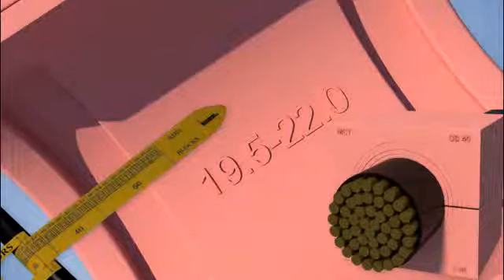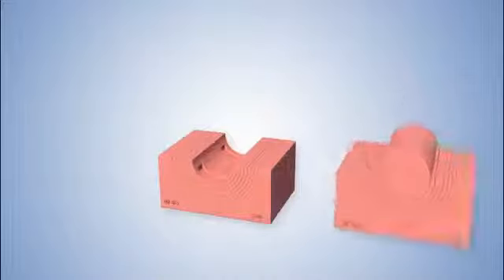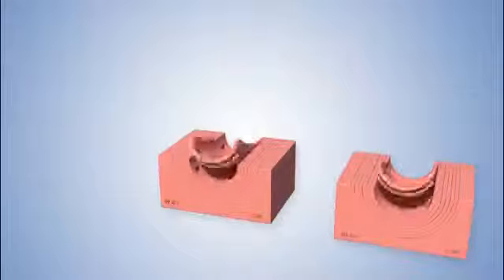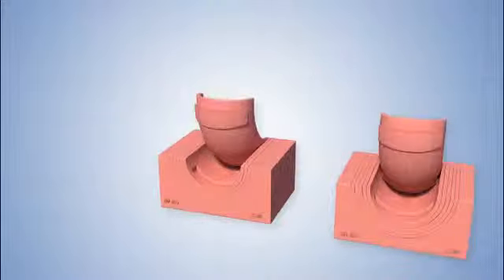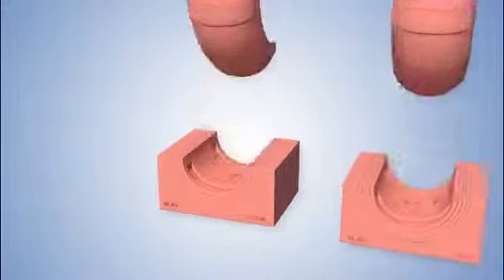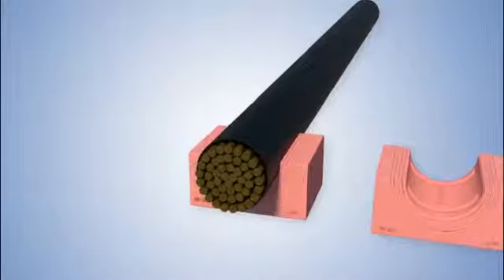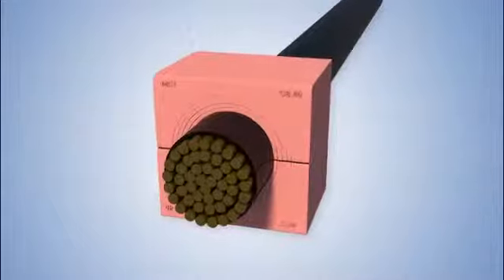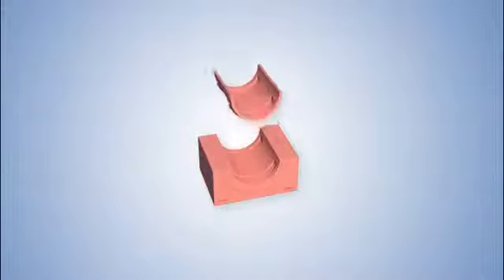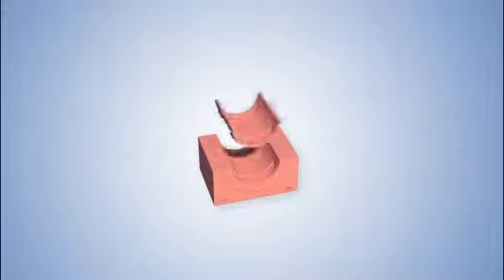To install, peel off the correct layer from the CS module to seal the selected cable diameter measured with the cable selector. You should maintain a gap of 0.1 mm to 2 mm between the prepared halves of the module as additional verification.